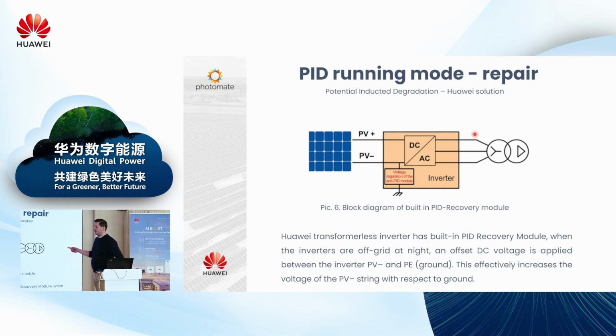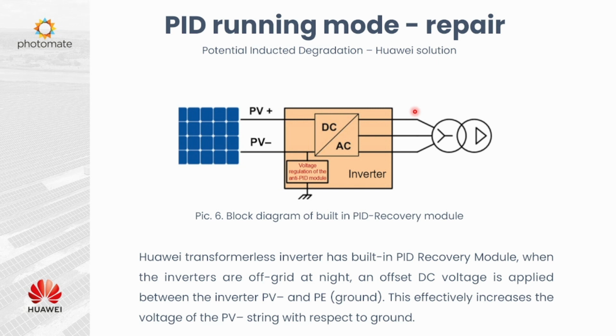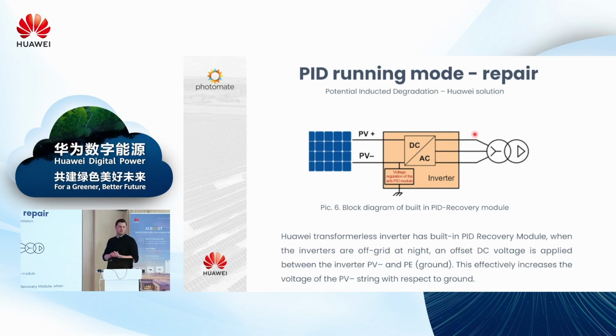So what's the solution? If you just enable this function in the inverter, it will raise the potential between the negative pole and the ground, and will repair your modules during the night. It's no harm for PV modules. Don't worry, nothing wrong will happen, but during the night it will just consume an additional 5 watts of active power from the grid. So test it please. If you already have PV installations with Huawei inverters, it's a very useful function.